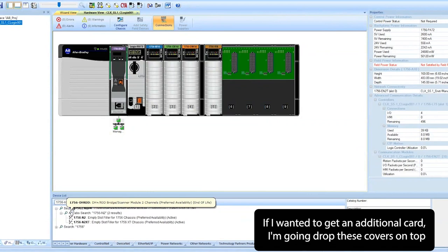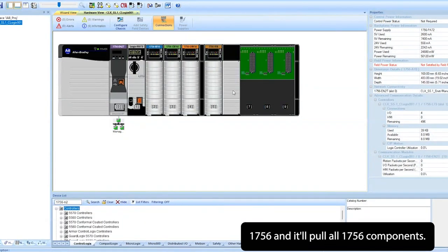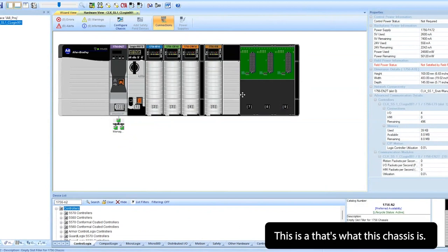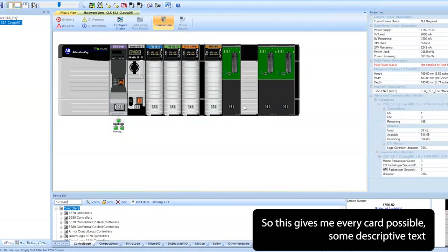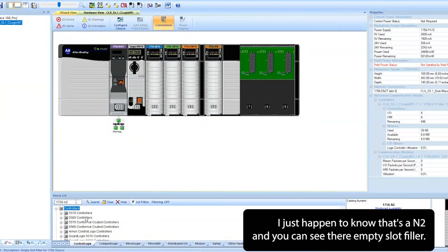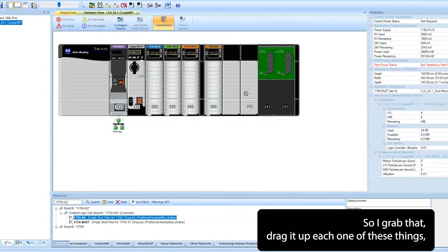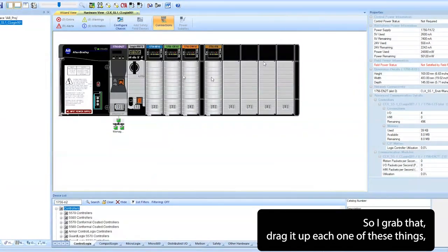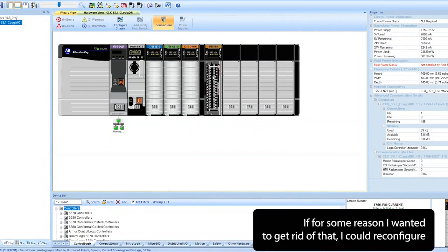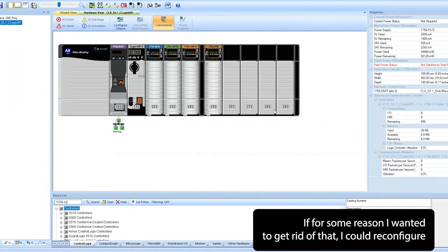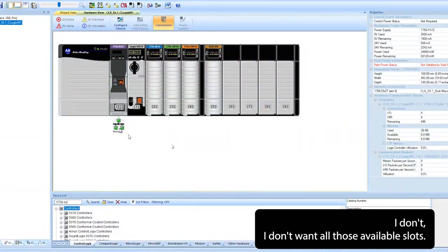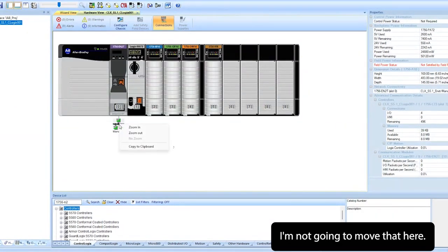If I wanted to get an additional card, I'm going to drop these covers on top just to show you how that works. 1756, and it'll pull all 1756 components. This is an N2, that's what this chassis is, so it gives me every card possible with some descriptive text. I just happen to know that's an N2 and you can see their empty slot filler. So I grab that and drag it up, each one of these things. It shows me my slot chassis, the zero through nine. If for some reason I wanted to get rid of that, I could reconfigure that chassis and say I want to take that down to a seven. I don't want all those available slots.